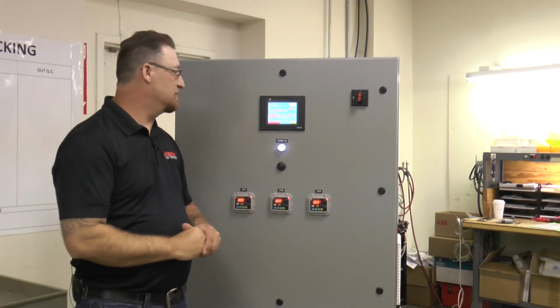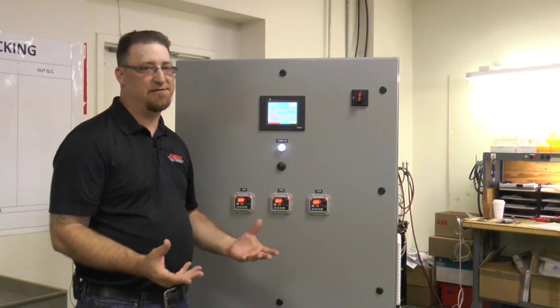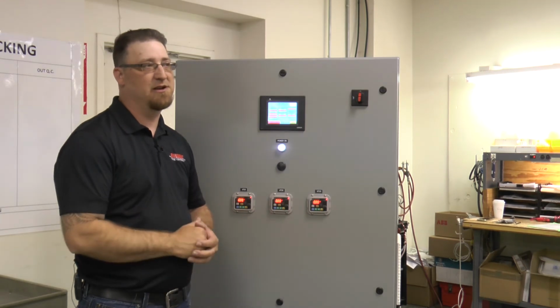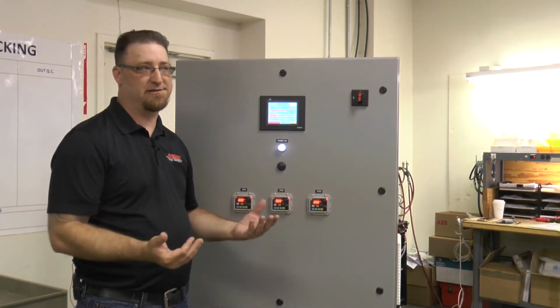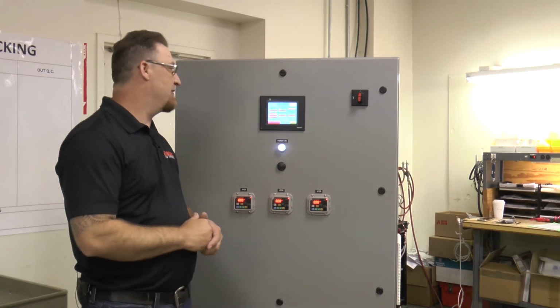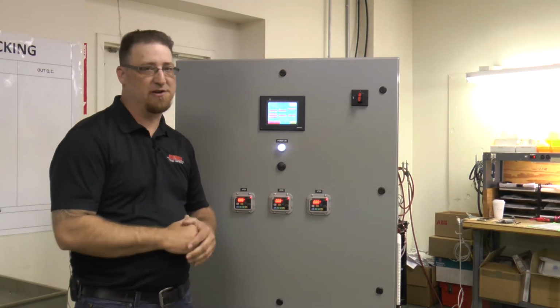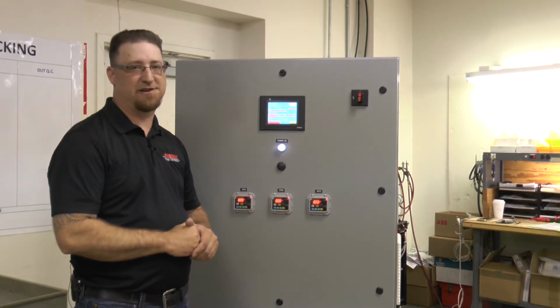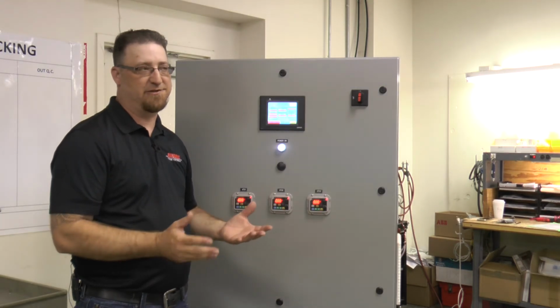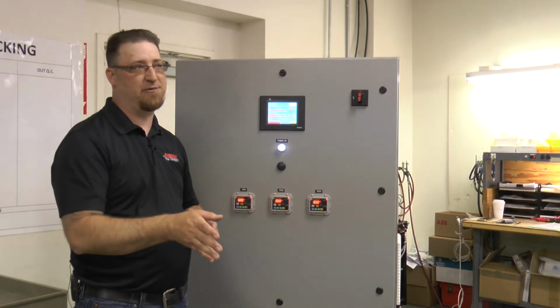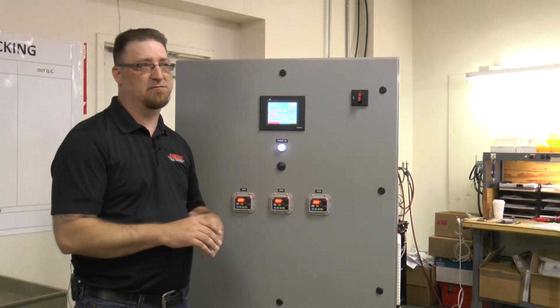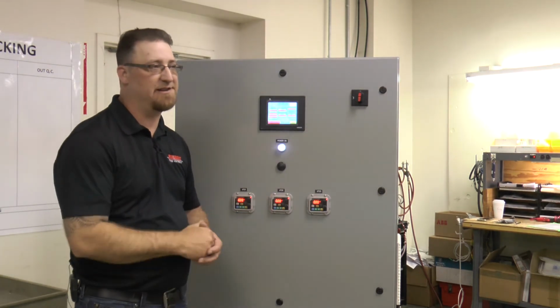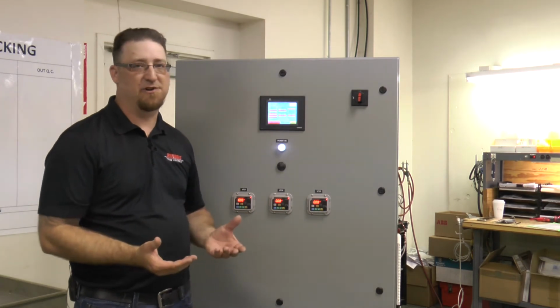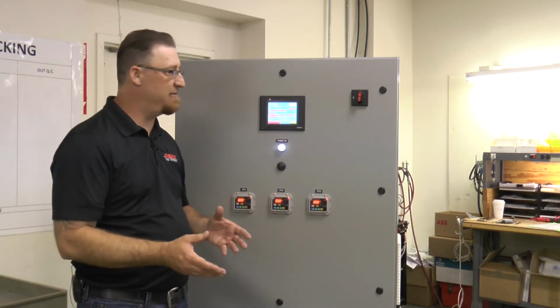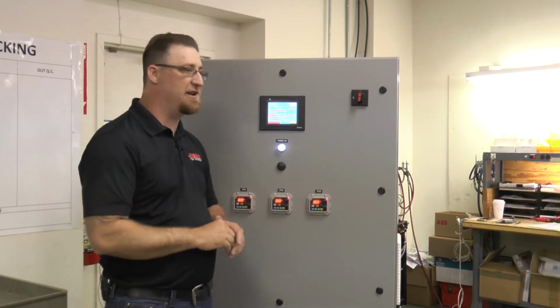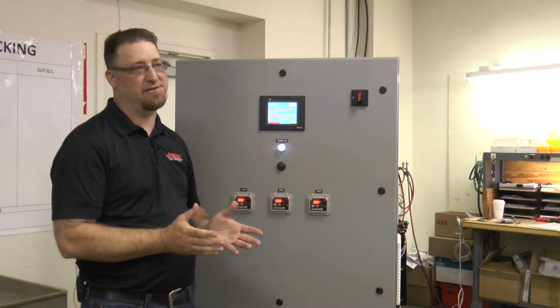And we also have a run mode button. So in local, the system runs automatically by itself. It'll turn on and turn off whenever it's called for, or your pressures are not met or they are met. We also have a remote mode. On your terminal strip, there's 2 terminals. So if you have something elsewhere in your system or at your facility to where you only need the pumps to run when you tell it to run and not automatically, you can switch to remote mode, and you just need a simple contact closure across 2 terminals.